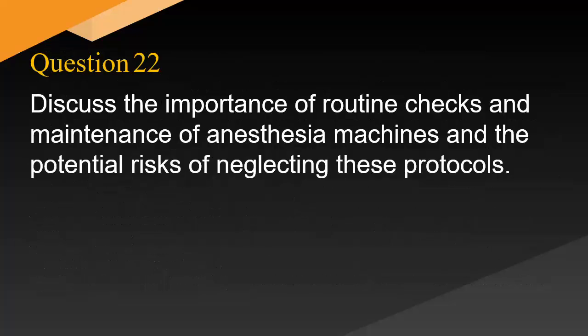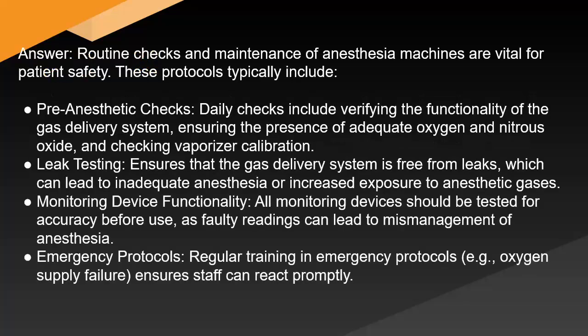Discuss the importance of routine checks and maintenance of anesthesia machines and the potential risks of neglecting these protocols. Answer: routine checks and maintenance of anesthesia machines are vital for patient safety. These protocols typically include pre-anesthetic checks. Daily checks include verifying the functionality of the gas delivery system, ensuring the presence of adequate oxygen and nitrous oxide, and checking vaporizer calibration. Leak testing ensures that the gas delivery system is free from leaks, which can lead to inadequate anesthesia or increased exposure to anesthetic gases.